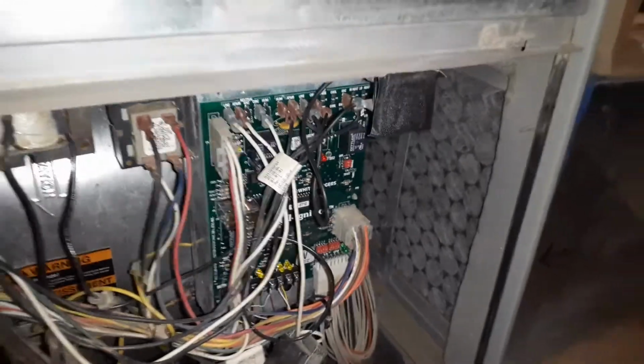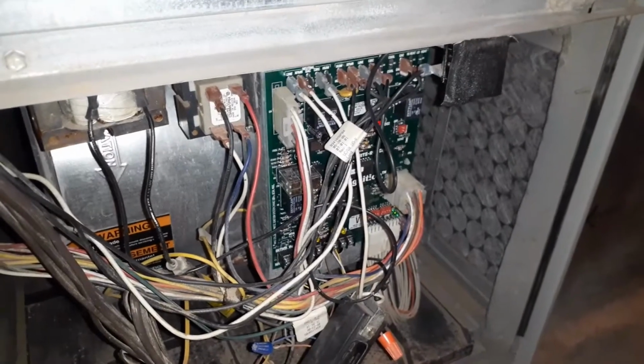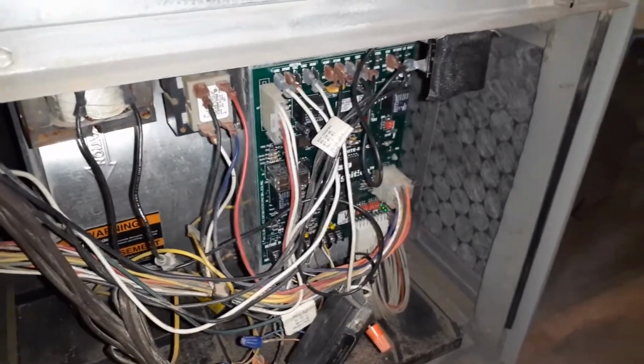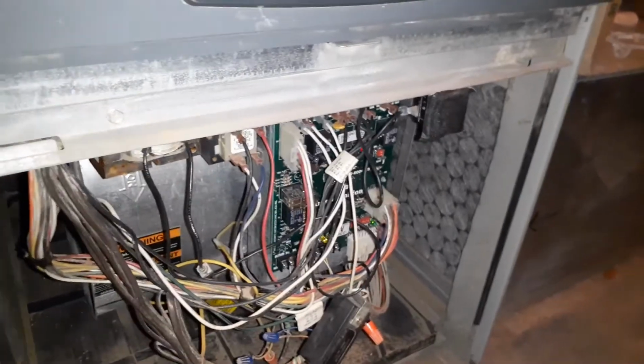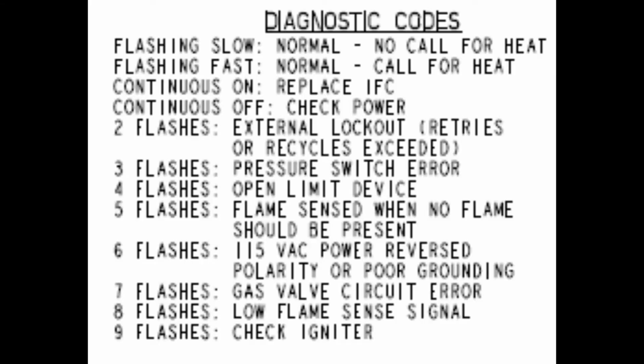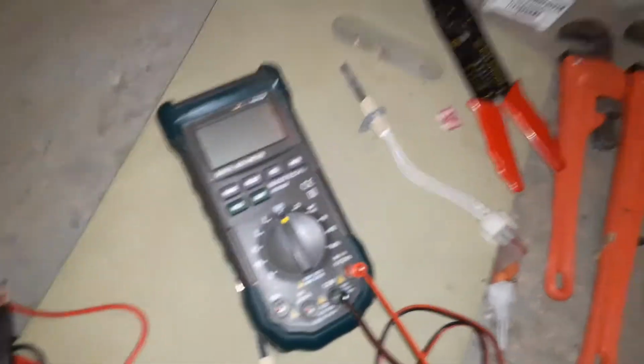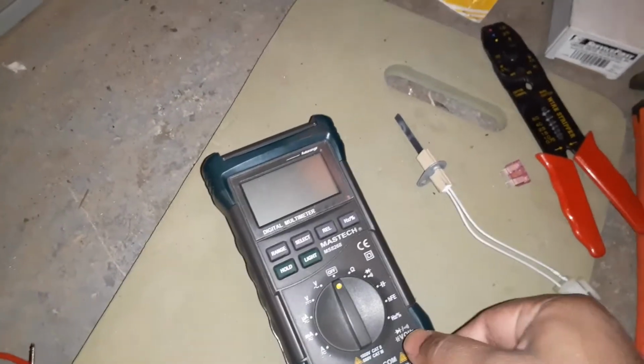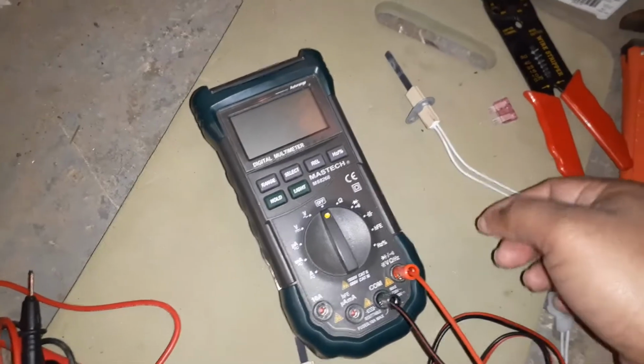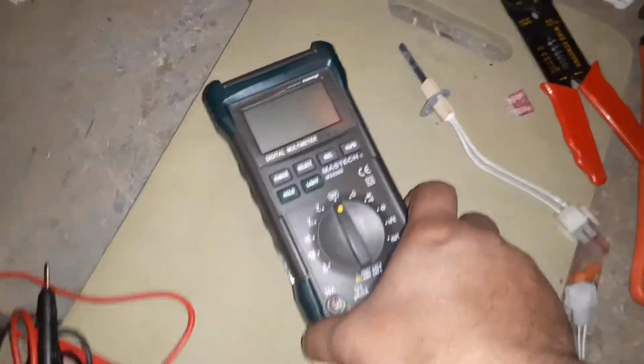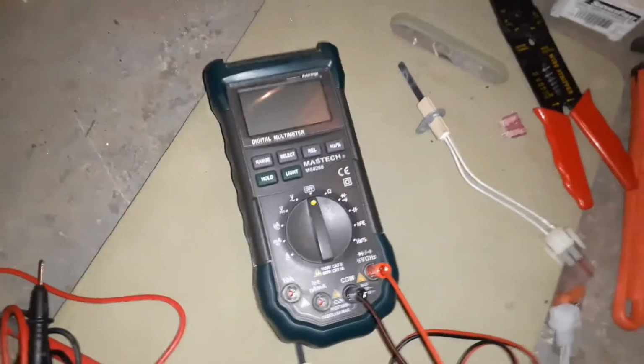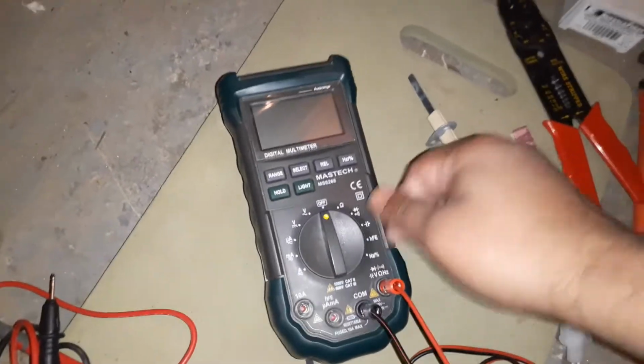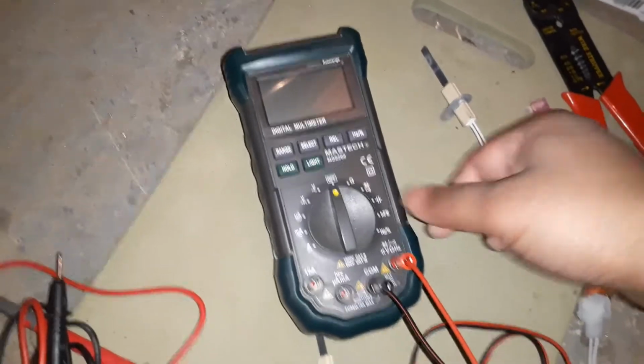You will see from the HVAC manual, or if you have the manual with you, or you can download it, it's the igniter. It's the error code for check igniter. You will need a multimeter or an ohm meter to measure the resistance to check if the igniter is good or bad. And usually if you get error code 9, it's very possible that your igniter needs replacement. And I will show you how I tested it.